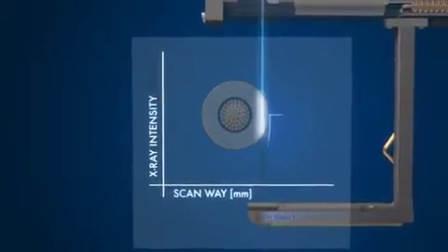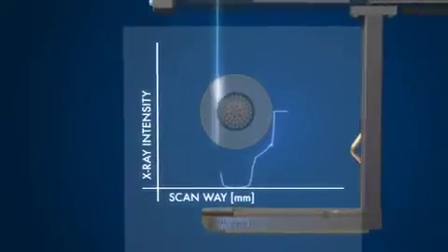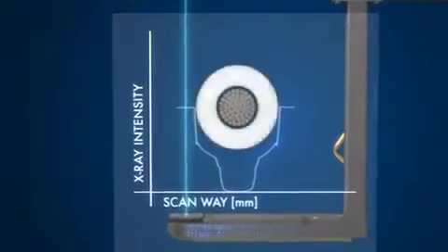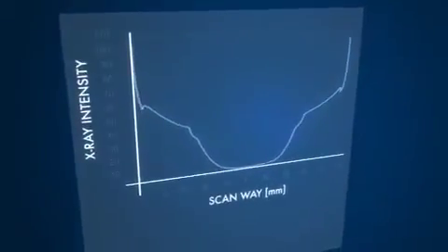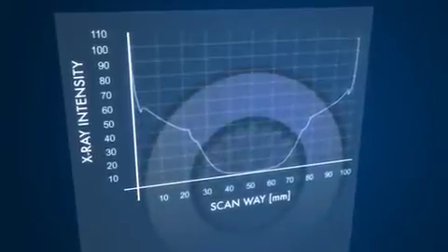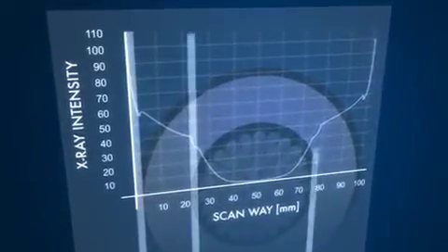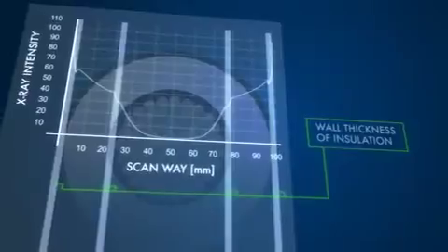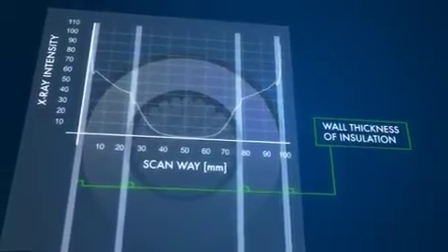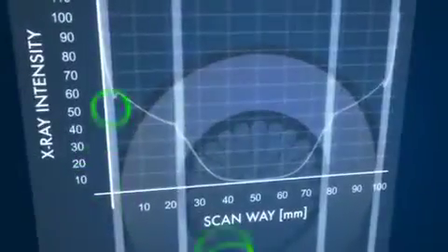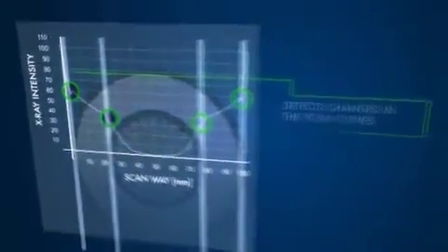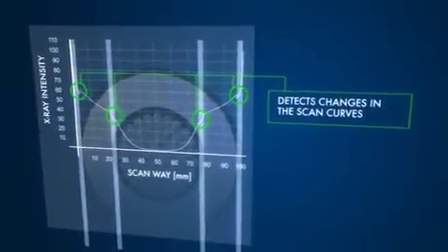The calculation of the measuring values of the cable results directly from the X-ray image. The radiation absorption changes at the layer transitions. All three layers of the cable, inner semiconductor, insulation, and outer semiconductor, can be measured. The transition points between the three insulation layers are clearly visible.